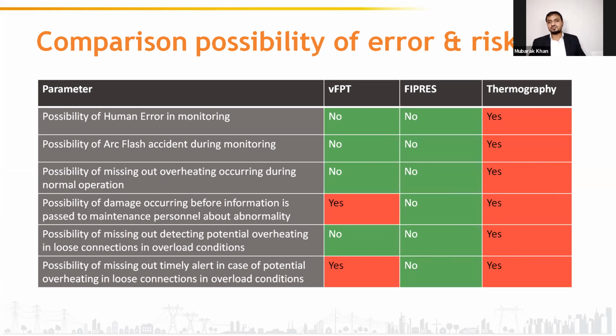Recently, there have been many fires in hospitals, and mostly the fires are due to improper maintenance. A lot of different factors are there, but there is one common problem, and that is overloads. So many pieces of equipment are plugged into the electrical circuit. The joints and the cables are getting overheated, and nobody is there to detect it. Right? Such scenarios may be avoided to some extent by using FIPRES. Possibility of missing a timely alert in case of potential overheating in loose connections in overload condition: yes, it is possible in VFPT, but not possible in FIPRES.